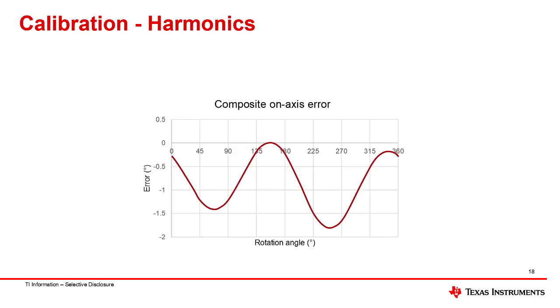Another method, which requires more effort and characterization, is to determine the cyclical error and then correct for it using harmonic reduction. The goal here is to determine the factors for each harmonic to use when adjusting the output angle. While this approach requires a more detailed calibration to reach peak performance, the final accuracy is greatly improved.